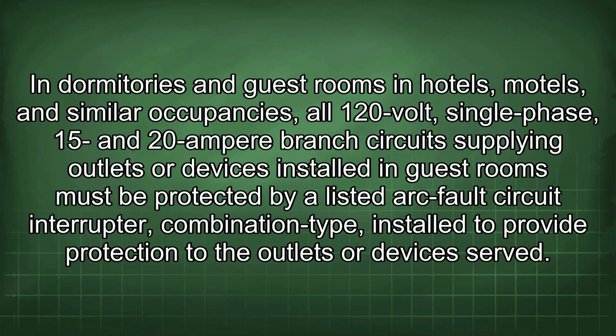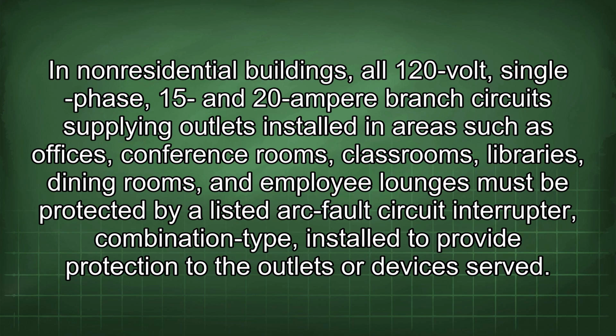In dormitories and guest rooms in hotels, motels, and similar occupancies, all 120-volt, single-phase, 15 and 20 ampere branch circuits supplying outlets or devices installed in guest rooms must be protected by a listed arc fault circuit interrupter combination type, installed to provide protection to the outlets or devices served. In non-residential buildings, all 120-volt, single-phase, 15 and 20 ampere branch circuits supplying outlets installed in areas such as offices, conference rooms, classrooms, libraries, dining rooms, and employee lounges must be protected by a listed arc fault circuit interrupter combination type, installed to provide protection to the outlets or devices served.